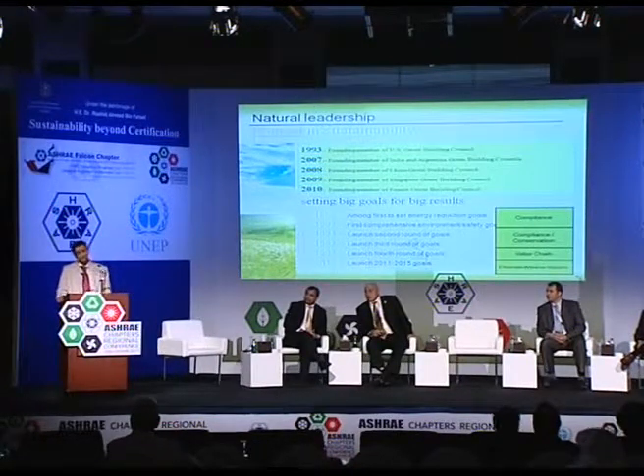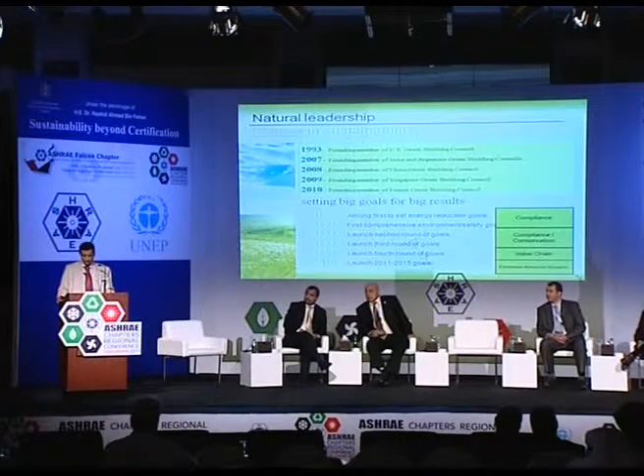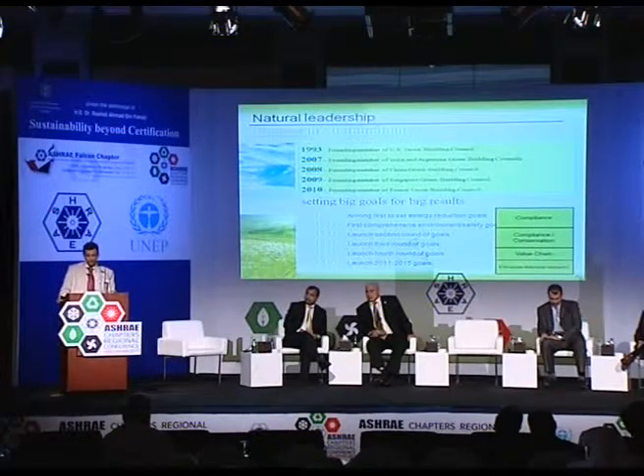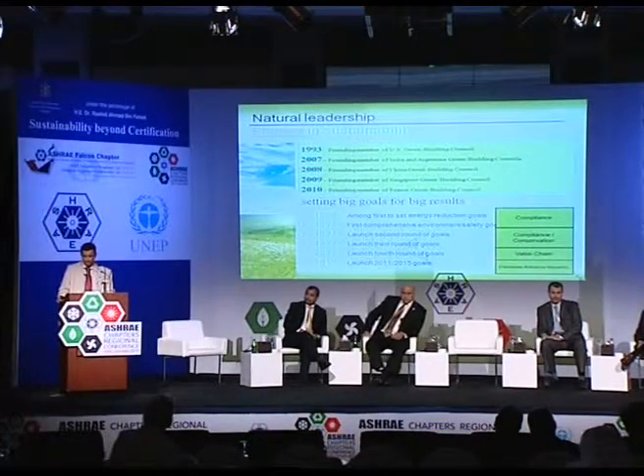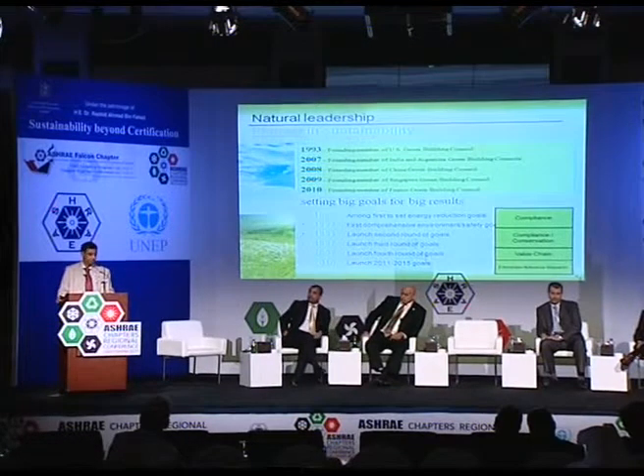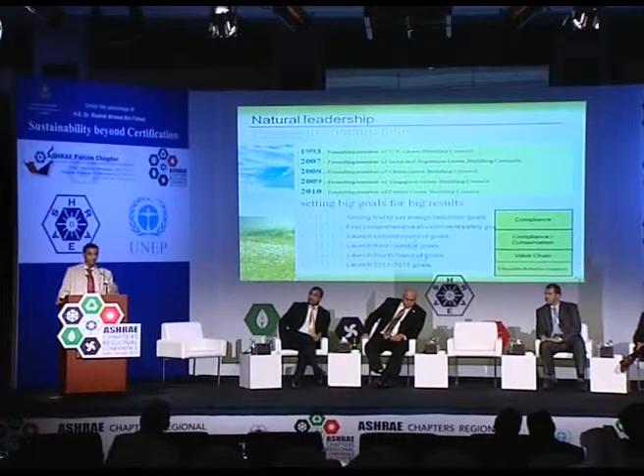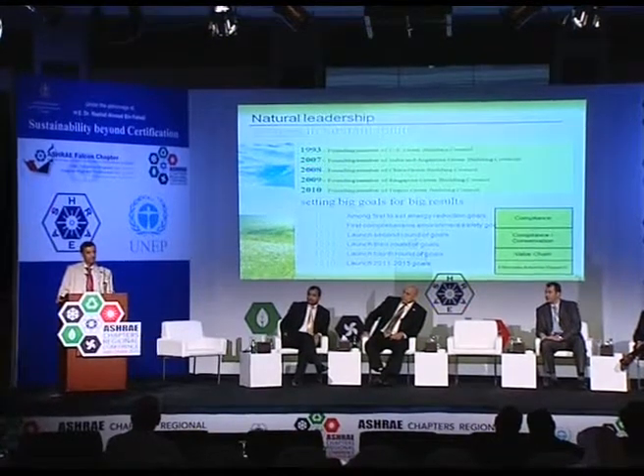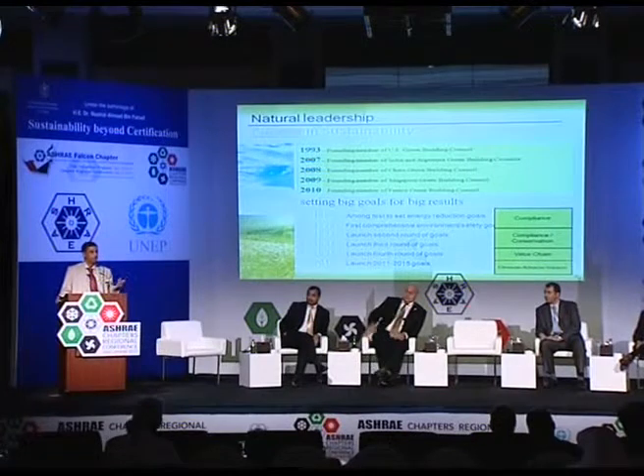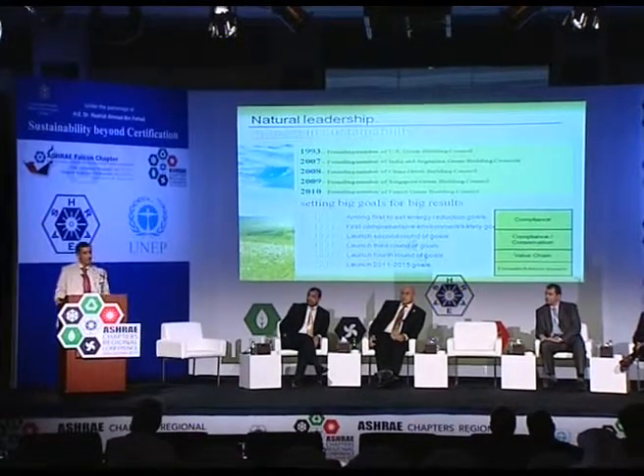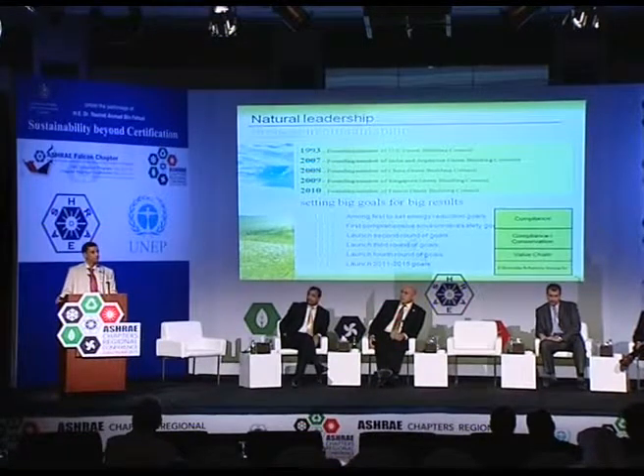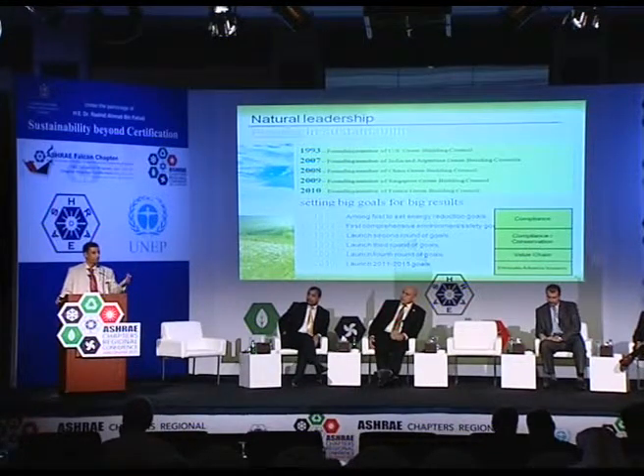The second observation is that new high efficiency systems utilize larger outdoor coils, improving high ambient performance. The EER of these new systems at 35 degrees centigrade is representative of average Middle East year-round performance - effectively an equivalent SEER for our region. This means that if a unilateral approach is taken within the GCC countries to use the ASHRAE 90.1 EER as a standard, applying a degrading factor based on high ambient conditions could be a good measure. That's what we observed.